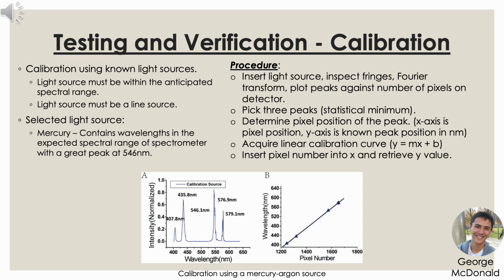And what you would obtain, if you look at image B on the bottom, is what's called a calibration curve, and it's really just a line. So this is a linear calibration curve, and once you have all the pixel numbers, from the equation that represents this line, you can plug them into X and then retrieve all of your wavelength values, which in this case is the Y value. And once you have all your Y values, you are now calibrated.